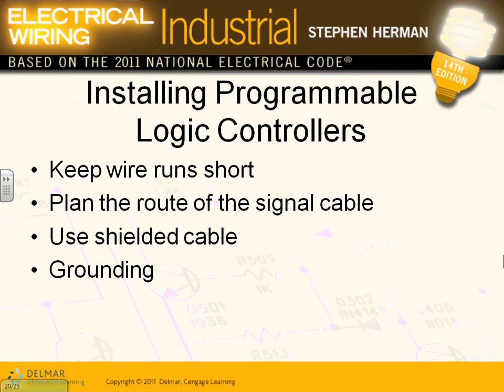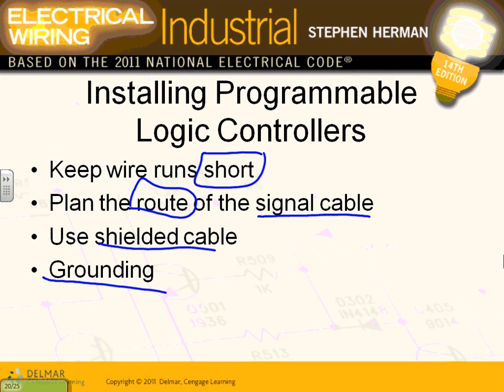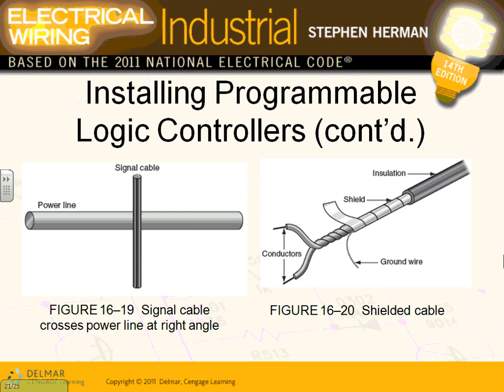Okay, so installing programmable logic controllers. A couple of hints when you put them in: keep your runs short because of voltage drop and a bunch of other interference and so forth. Plan the route so nobody can interfere with the route that you're going to put for your signal cables. Shielded cables, good idea. Grounding, you have to ground the system. All your equipment has to be sitting at the same ground, because if you have a ground difference between the neutral and the ground, 5 volts, that could interfere with your input-output devices. So these are a couple of hints that you have to keep in mind.